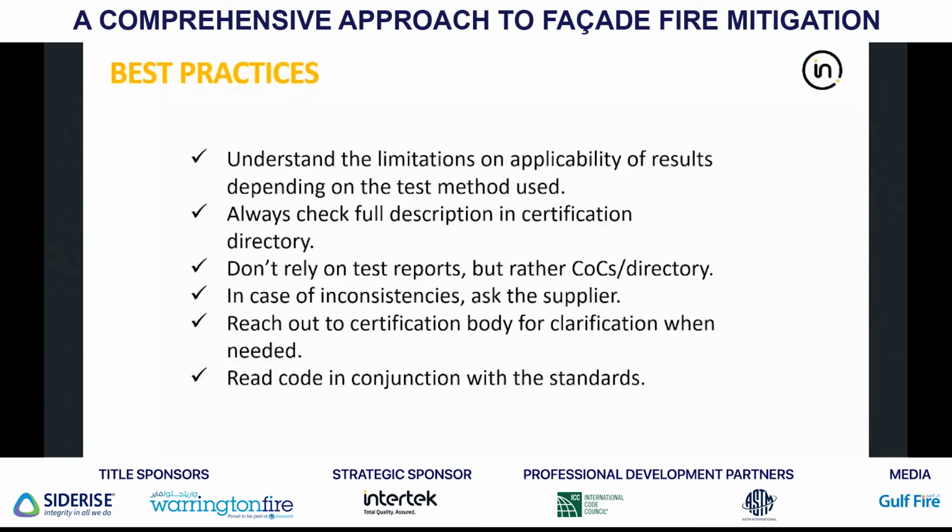One thing, don't rely on test reports, okay? We're talking about systems. Sometimes one system is based on 50 test reports. So don't focus on that. That job has been done already by the certification body. Focus on that deliverable, the COC or the directory, okay? That assessment has been made. In case of inconsistencies, always ask the supplier or reach out to the certification body for clarification when needed, okay?